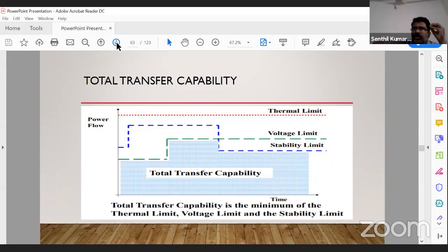In case of voltage variation, at that time we may allow up to 720 megawatts. If the environmental temperature is also lower, we allow up to 720 megawatts. In case of a line tripping, the other line could be allowed up to the thermal limit, that is 874 megawatts for the twin-moose conductor.